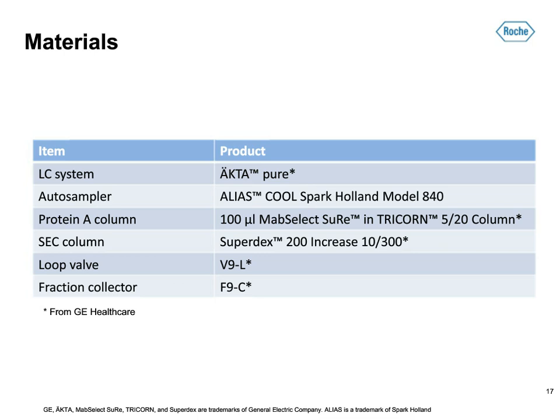As the size exclusion column, we are using the 10/300 Superdex 200 Increase from GE Healthcare, which allows us to run at higher flow rates than a normal S200 column, saving a lot of time. The loop valve allows the connection of five loops; we just need two. Before we got the F9-C fraction collector, we had the carousel fraction collector F920. Compared to the F920, the F9-C allows almost 600 fractions of 2 ml to be collected.